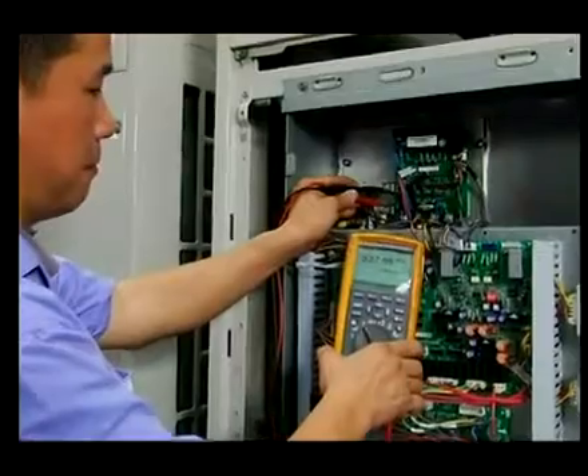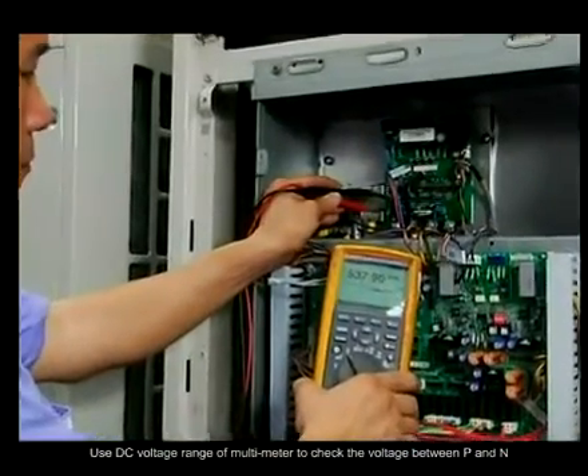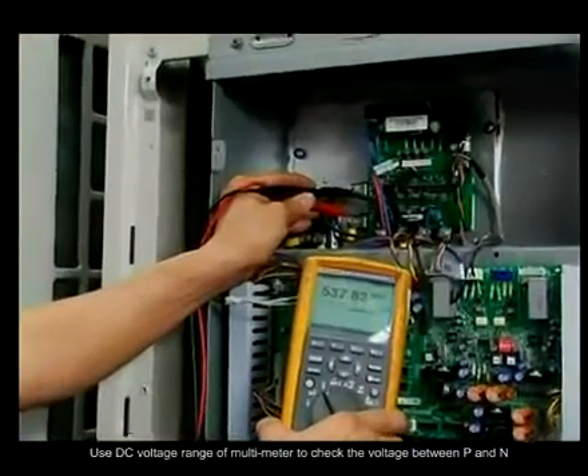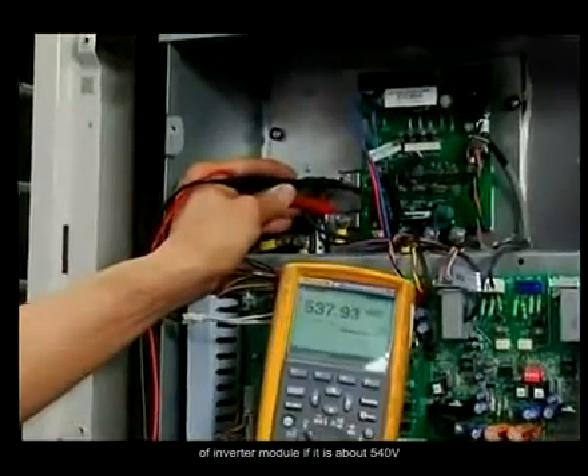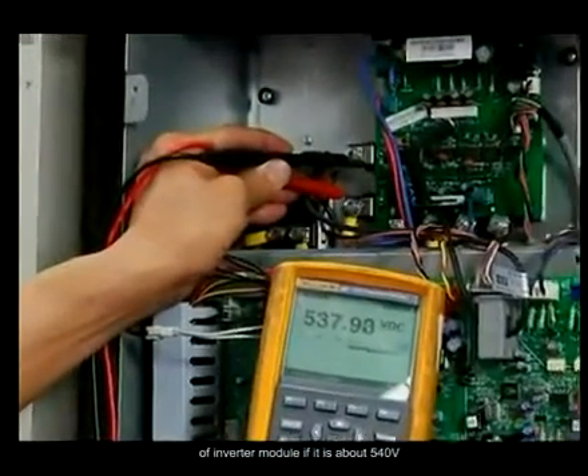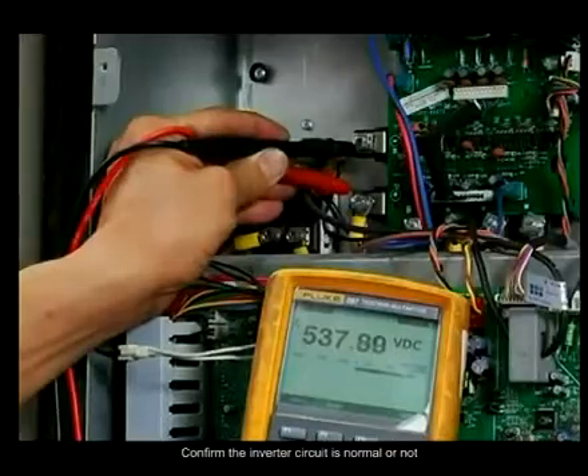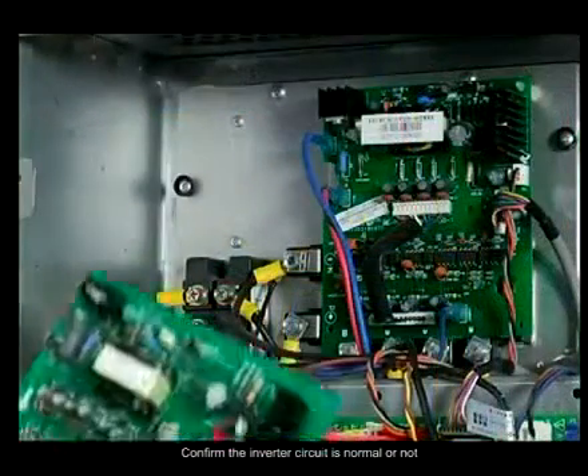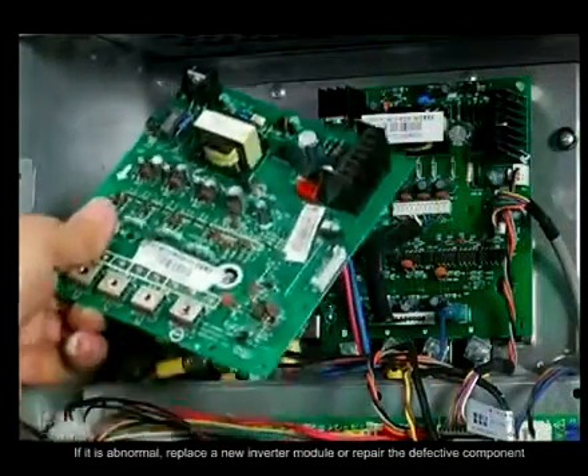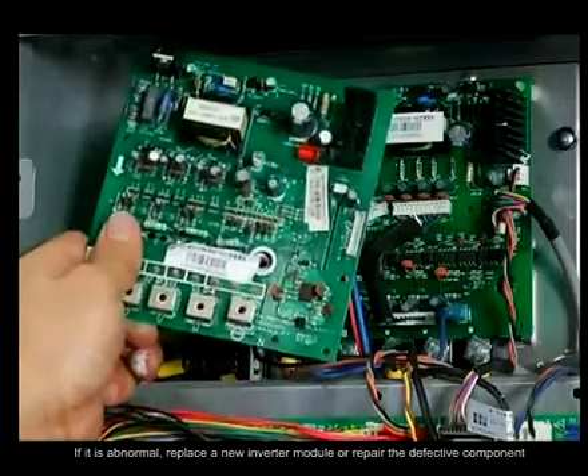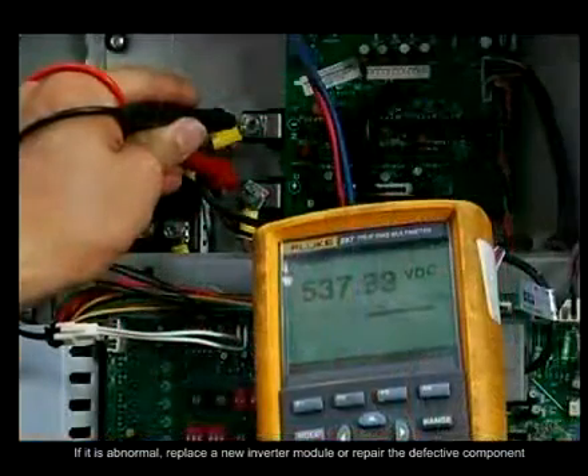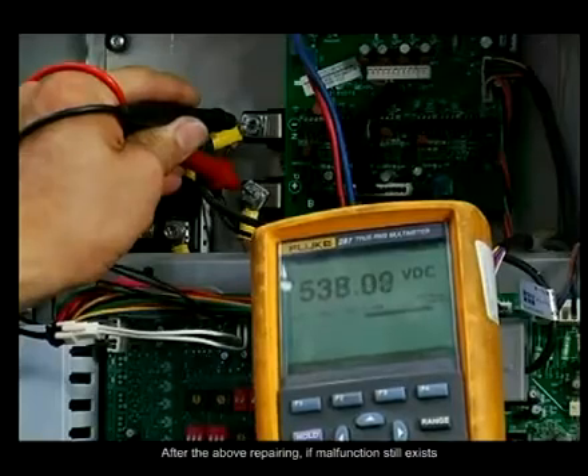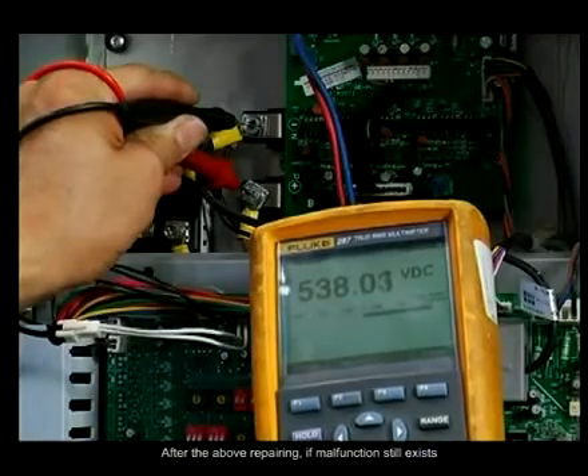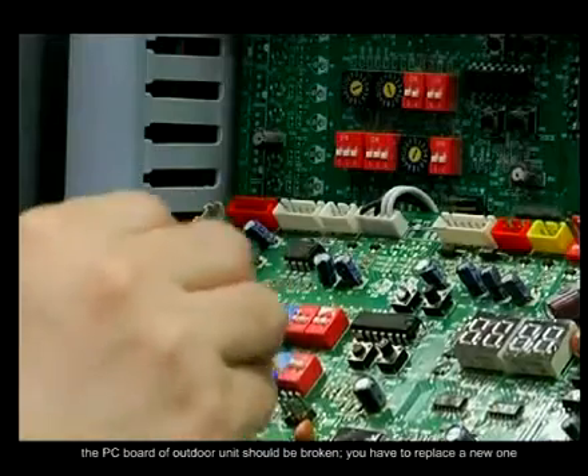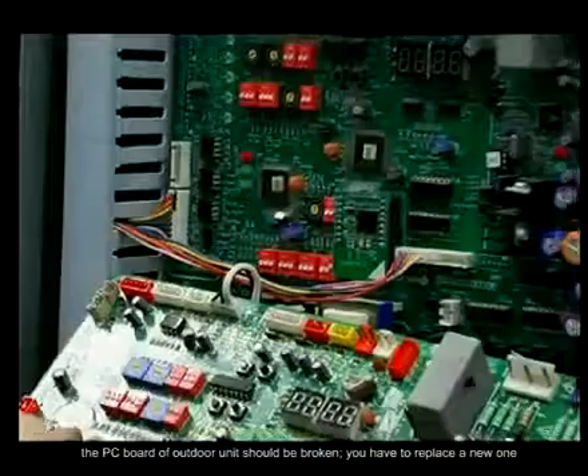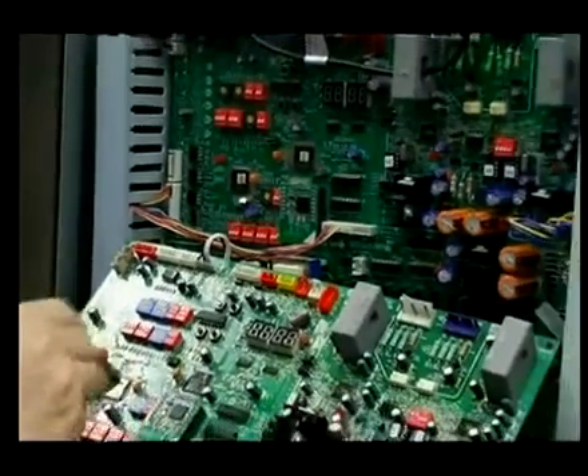Step 2. Use the DC voltage range of the multimeter to check if the voltage between P and N of the inverter module is about 540 volts. Confirm whether the inverter circuit is normal or not. If it is abnormal, replace with a new inverter module or repair the defective component. After the above repairing, if the malfunction still exists, the PC board of the outdoor unit may be broken. You have to replace it with a new one.